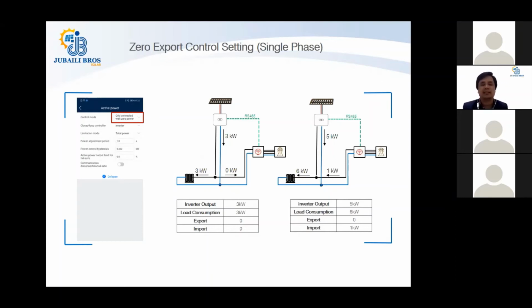Let's take the case where the generation is 4 kilowatt from the inverter, and the load is requiring only 3 kilowatt as shown. Since the generation capacity is more than 3 kilowatt, which is the requirement of the load, the inverter will curtail power immediately to 3 kilowatt. Thus the output power will be limited to 3 kilowatt, which is exactly the load requirement, and zero power will be fed towards the grid side.